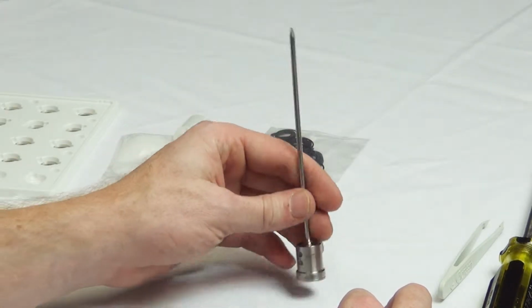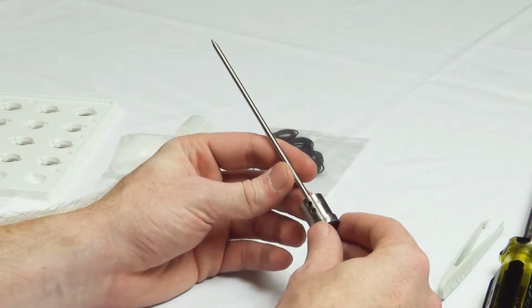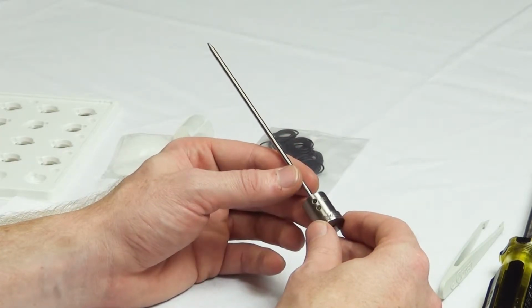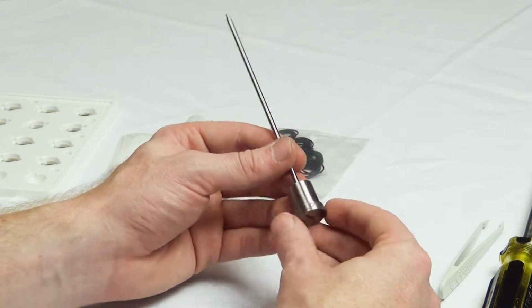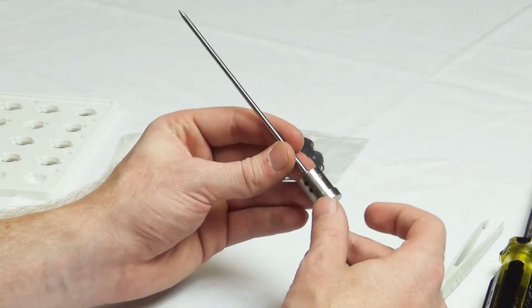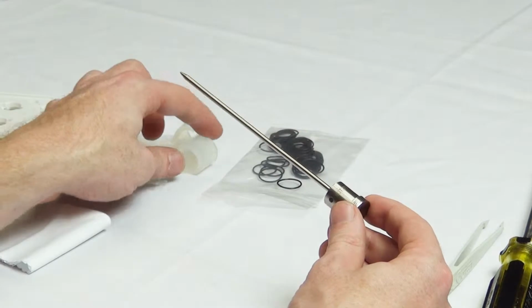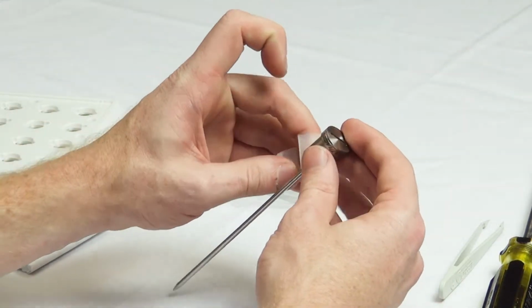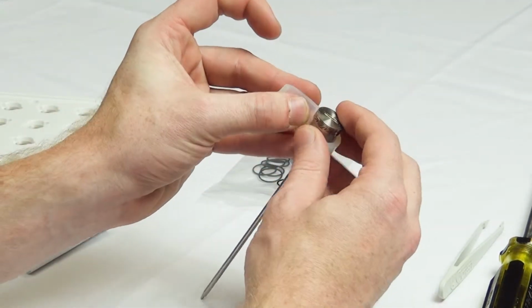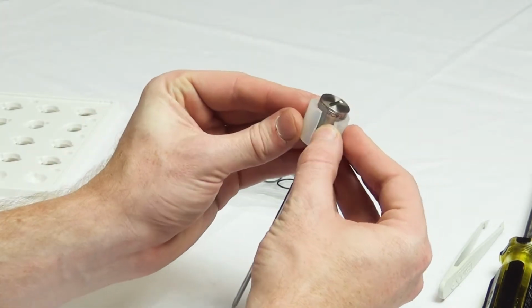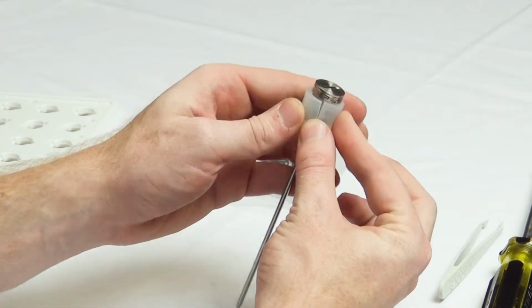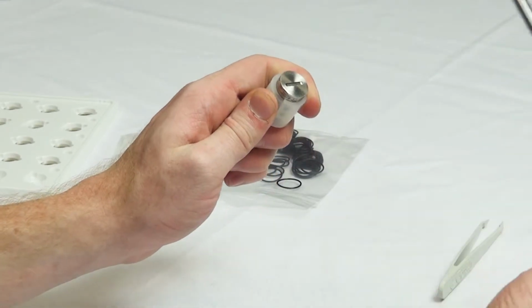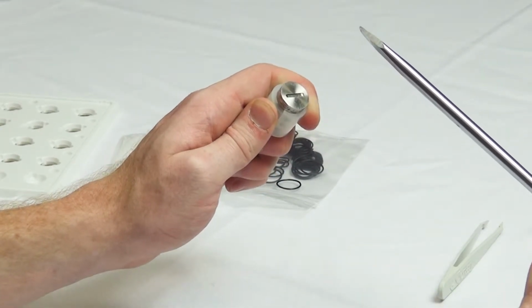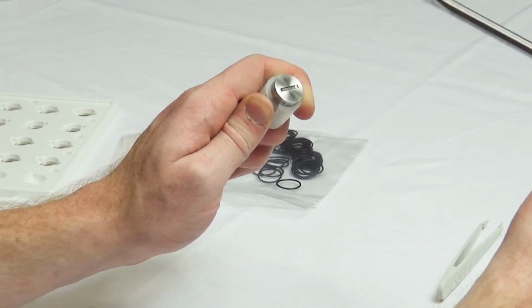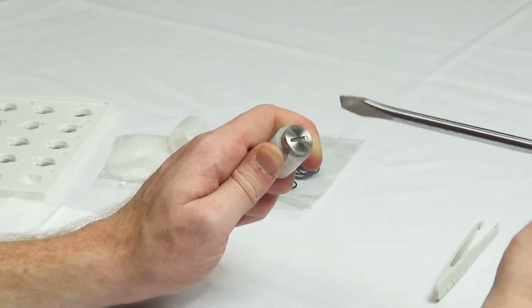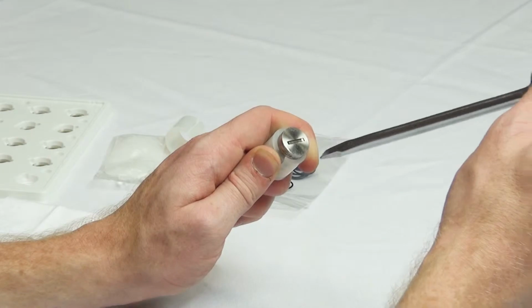First, take your logger and clean and dry the outside surfaces, making sure that they are clear of contaminants or debris. Then loosen the battery cap with the logger gripper provided by holding the logger in one hand with the probe facing toward the ground, placing the logger gripper over the body like so, and twisting the battery cap counterclockwise with the other hand using a coin, like a nickel, or a flathead screwdriver.